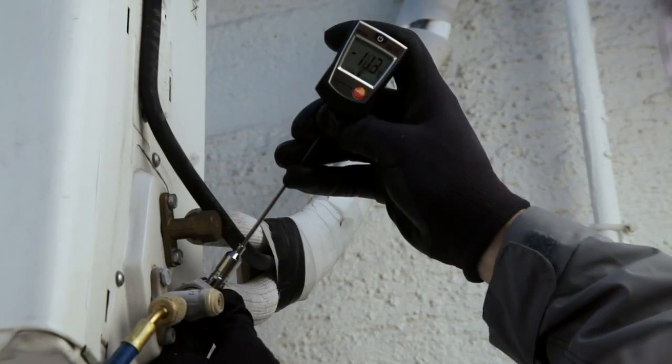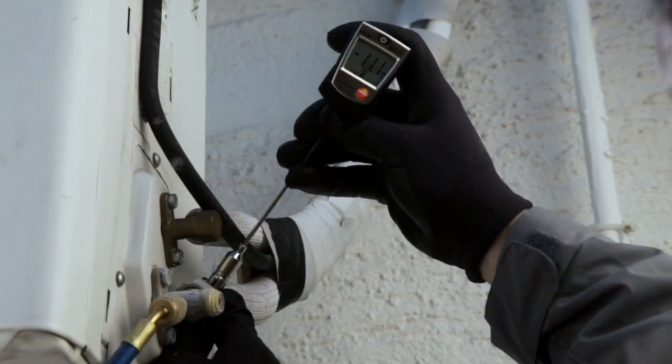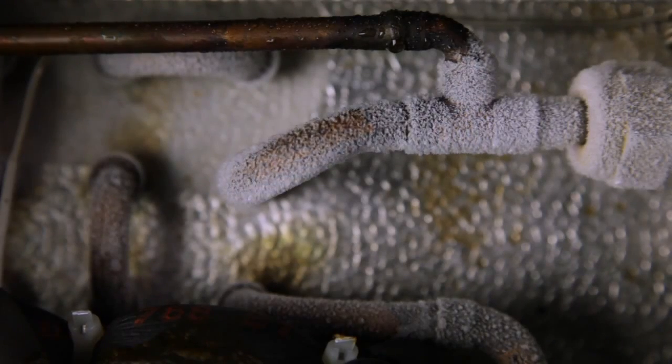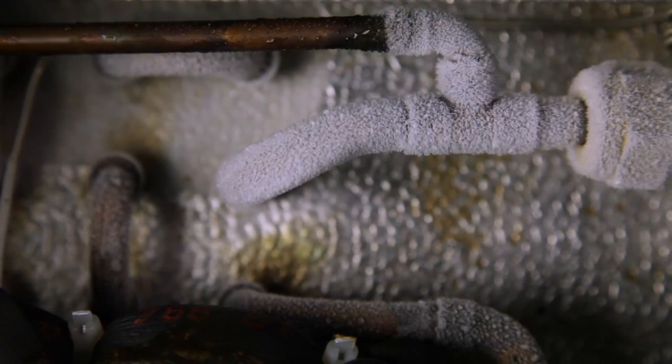The correct refrigerant filling quantity and the exact determination of superheating and sub-cooling are crucial parameters. If these are incorrectly adjusted, the system has higher energy costs and a lower refrigeration performance than originally intended.